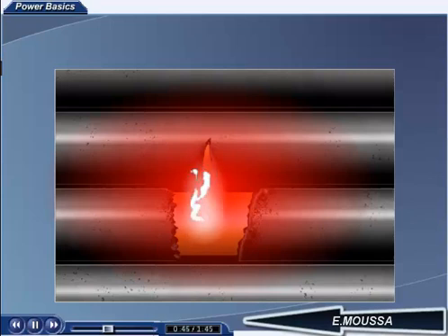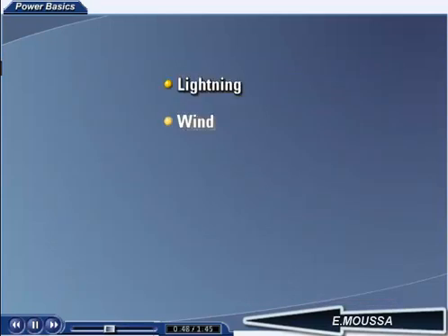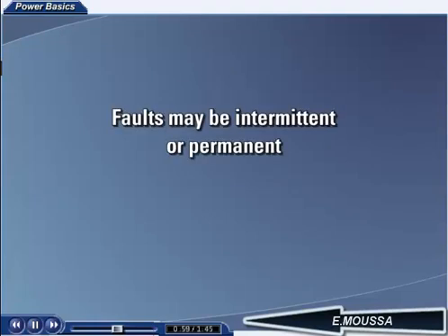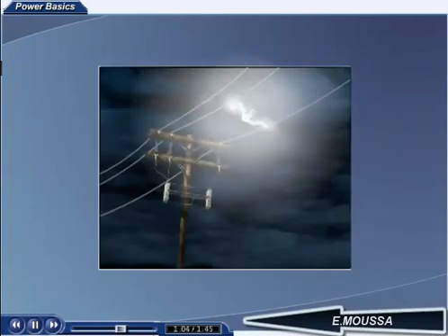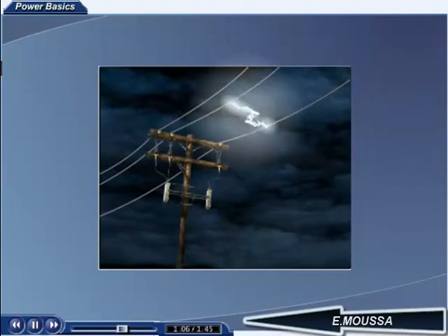There are many causes of power system faults: lightning, wind, and ice and snow, just to mention a few. The protective system must be able to sense the fault and take appropriate action within a time frame necessary to minimize damage. Faults may be intermittent or permanent in nature. Lightning striking the transmission line, or a strong wind causing 2 phases of the transmission line to touch and form an arc are common causes of an intermittent fault to an overhead transmission line. The resulting arc ionizes the air and turns it into a conductor. The arc is then maintained by the power in the line.